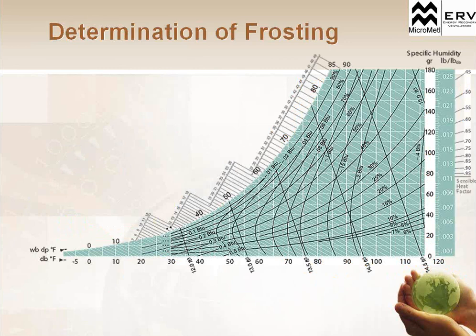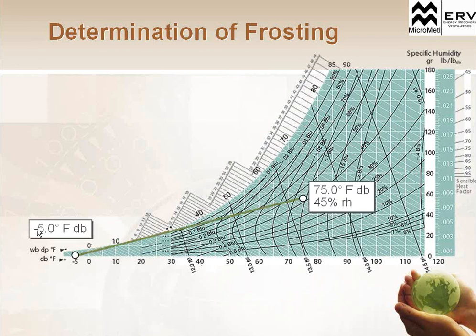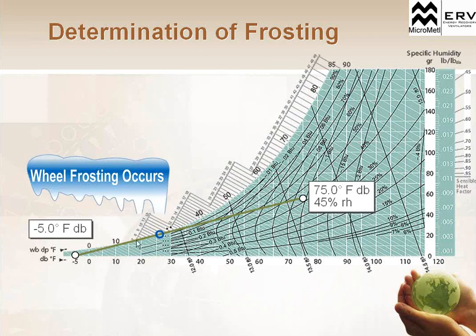Frosting is another issue. So we had motor location we want to be aware of when we're installing energy recovery units, and also frosting. Because we are bringing in cold outside air during the winter, and we have warm inside air coming out, there is a potential for frosting in those colder climates. So in a situation where we had negative 5-degree outside air, and we're bringing in 75-degree inside air at 45% relative humidity, we actually cross that dew point line and we can get frosting on that energy recovery wheel.